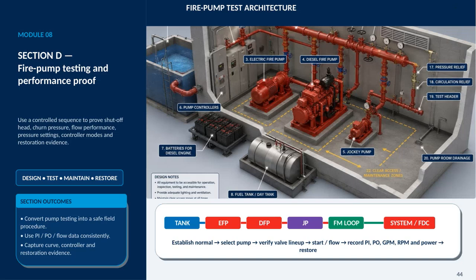This module focuses on turning fire pump testing into a controlled, repeatable field procedure. The goal is not simply to start the pump and observe flow. It is to prove the complete performance picture, including shutoff head, churn pressure, flow performance, pressure settings, controller modes, and evidence that the system was properly restored afterward. The central sequence is: establish normal conditions, select the pump, verify the valve lineup, start and flow the system, record the required data, and restore the system. That sequence creates a consistent path from preparation through closeout, while reducing the risk of missed steps or incomplete documentation.